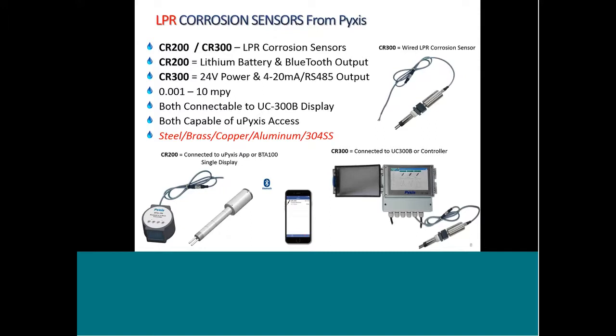Simply by screwing it into a flow line of a 1-inch NPT and utilizing this device in a Bluetooth mode, capture your corrosion data. And it also offers both general and localized corrosion in those same 5 metallurgies, and would be configured and data uploaded utilizing that same app called uPyxis that we would use for the level sensor.